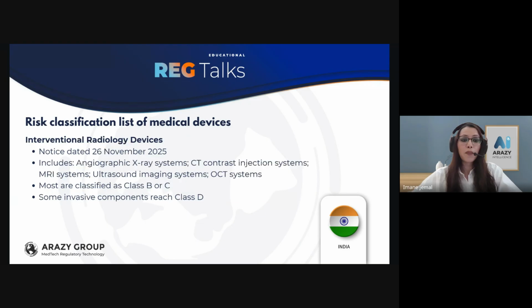For the interventional radiology notice issued on the 26th of November of last year, it covers diagnostic and image-guided systems such as angiographic system, CT contrast injector, MRI equipment, ultrasound system, and optical coherence tomography systems. So most devices in this category fall under Class B or Class C, depending on the complexity and the patient interaction. However, the invasive intravascular component, particularly those introduced into the vascular system, may be classified as Class D in this case due to their high risk for the patient.